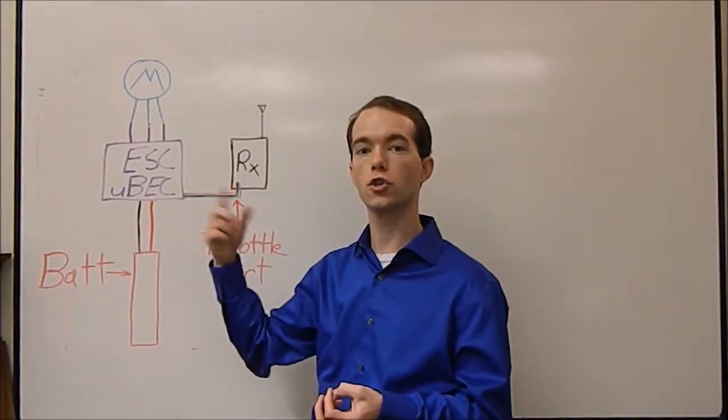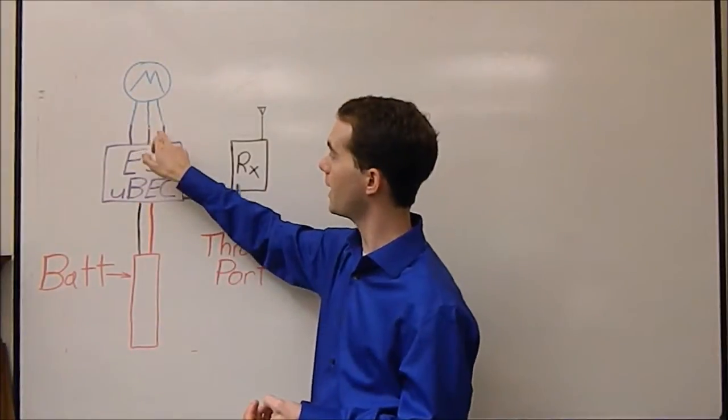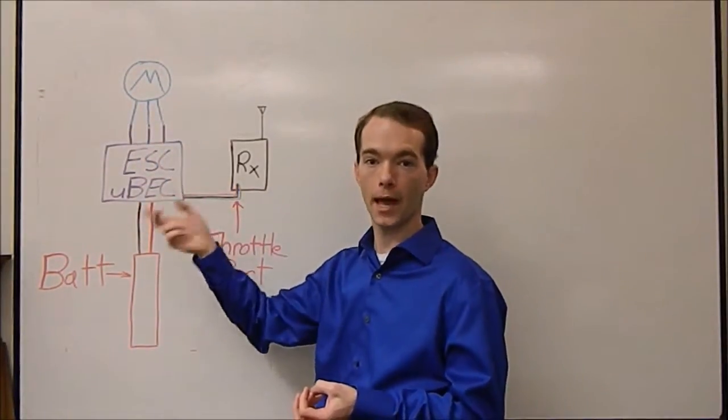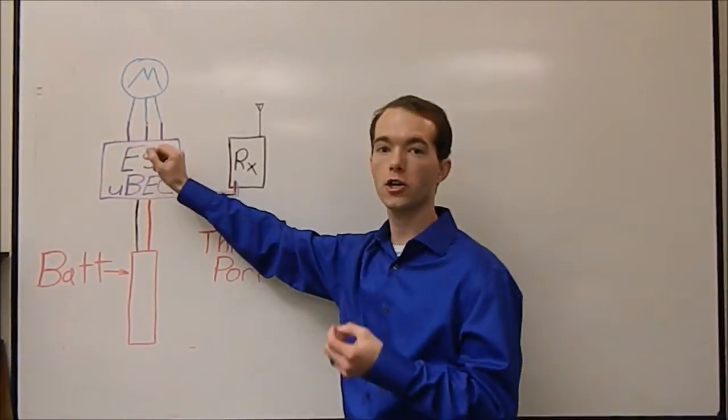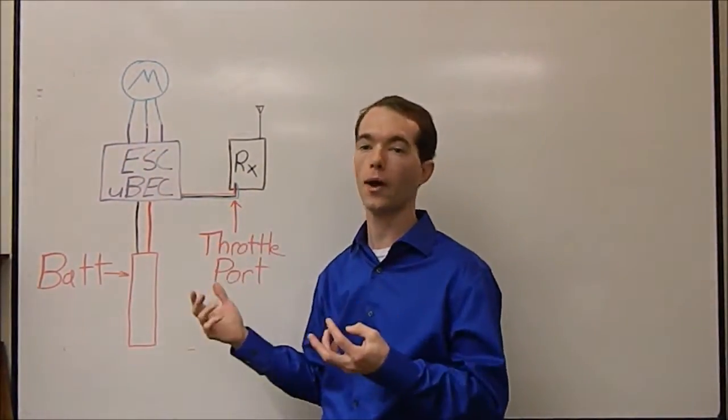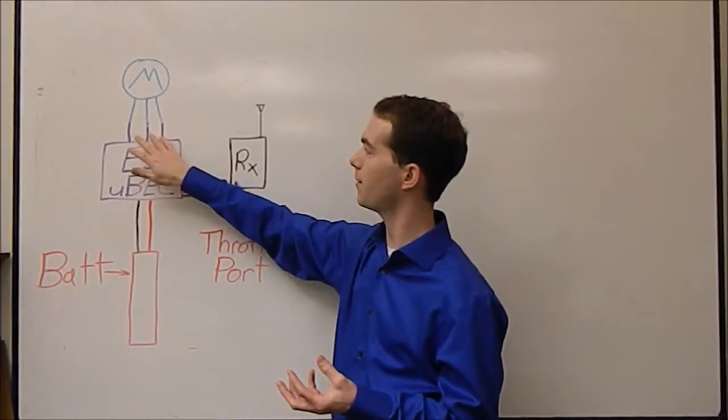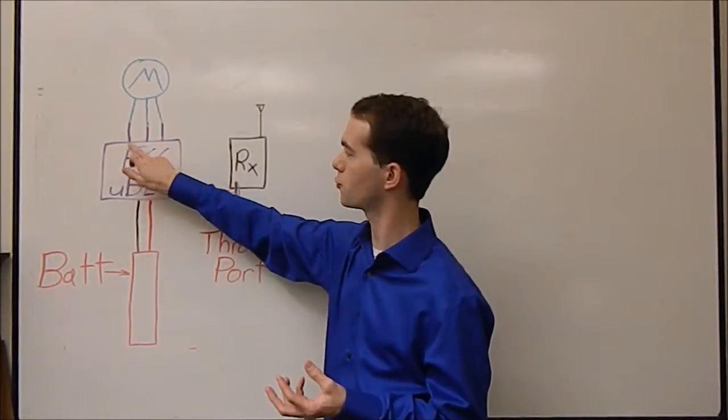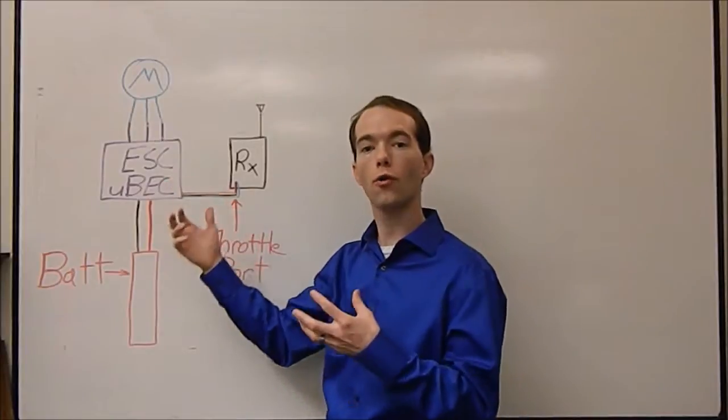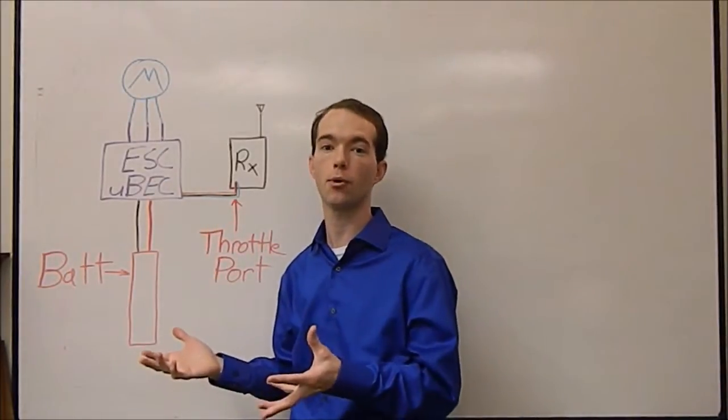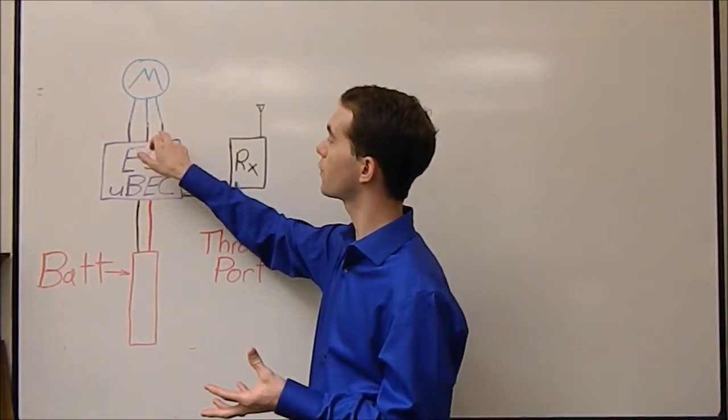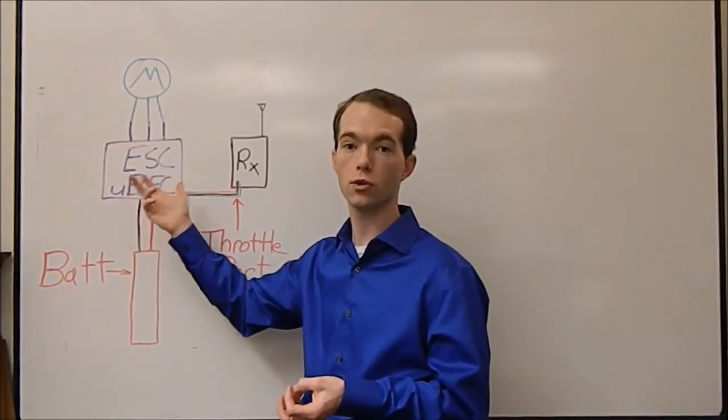If your motor turns the wrong way, simply pick any two wires and flip them, and it will reverse the rotation of the motor. So, you don't have to worry about that. That caused me a lot of confusion, because I had three black wires coming out of my motor and three funny colored wires with just letter labels here. All those are the different phases. Don't worry about the polarity, because there isn't polarity for AC. Just flip any two wires if your motor rotates the wrong way.